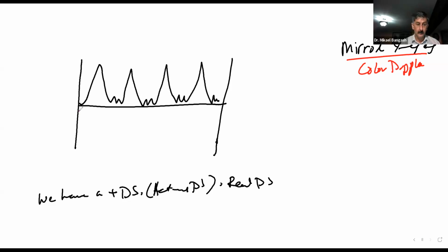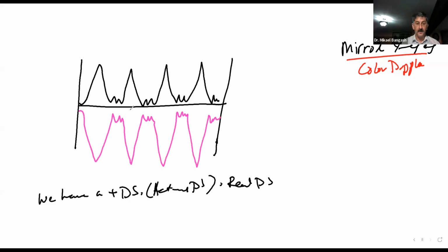It's going to be a true copy of your positive Doppler shift, which was real, and it's going to appear on the negative side there. So this negative Doppler shift recording here is fake, it's an artifact. And in this case, we call this artifact here crosstalk.